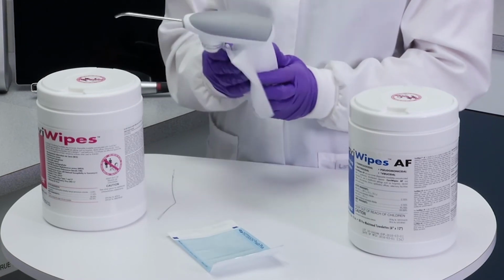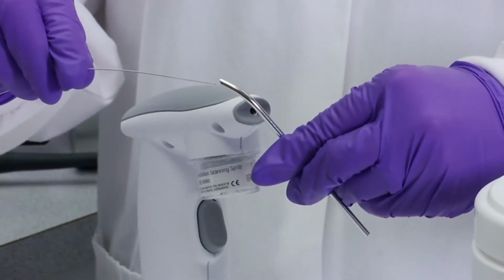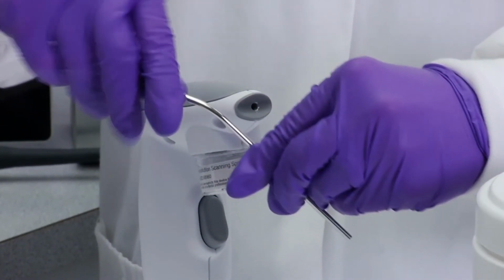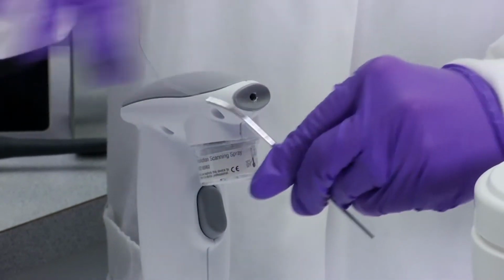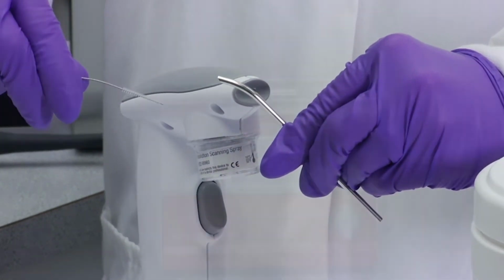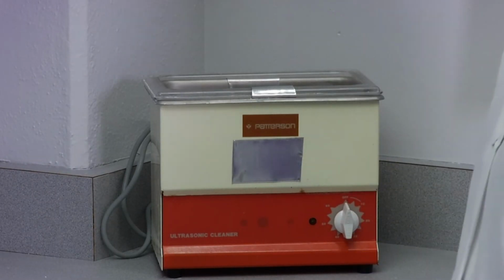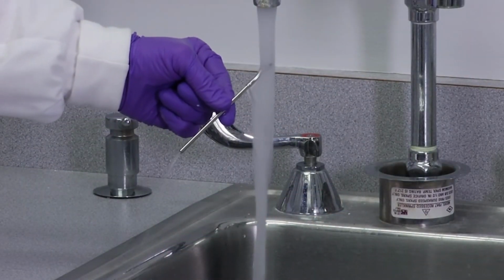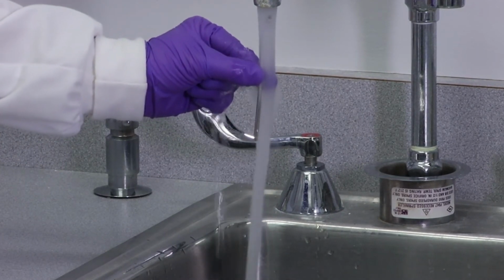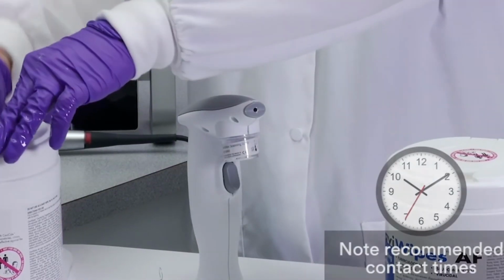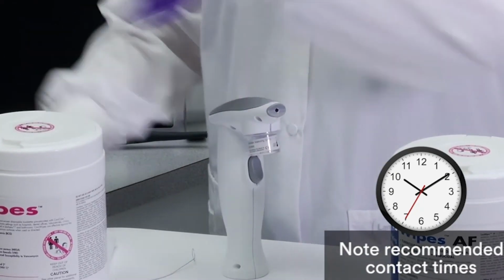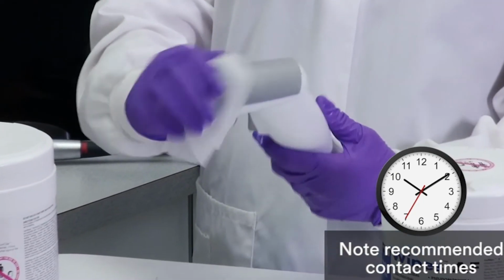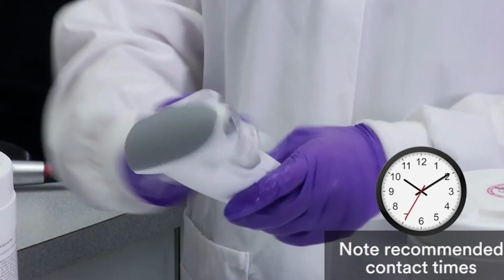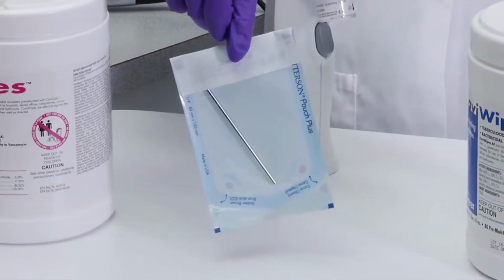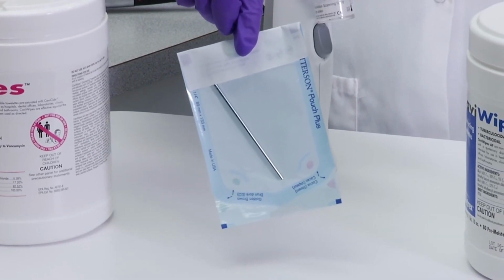When all surfaces have been wiped, discard of the wipe. The sprayer tip should be cleaned with the wire brush. It is important to note that you should clean the internal surface of the tip while dry. Once you have thoroughly cleaned the sprayer tip, run the tip through the ultrasonic. When complete, rinse under tap water and dry. For the disinfecting procedure of the sprayer, wipe down all surfaces with a new wipe. Allow for the recommended contact time per manufacturer. Allow a 3-minute contact time for CaviWipes and a 5-minute contact time for CaviWipes AF. Lastly, you will autoclave the sprayer tips in between each patient.